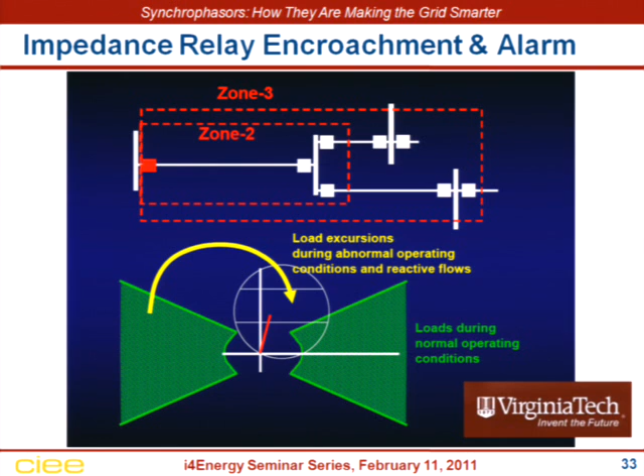That's what this represents. But if something happens and there's, say, a fault on the system and the system oscillates, you can have an operating point here, swing into here and back out. And when it swings into here, if it gets into here, that relay is going to trip. So what you want to do is keep tabs on this and look at these voltage excursions or these load excursions. And when they start getting close to this thing, then you want to think about doing a relaying study and reset your relays.